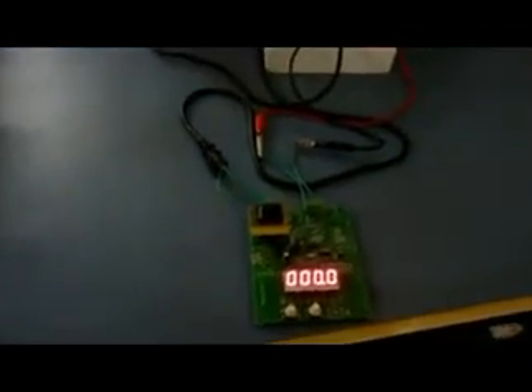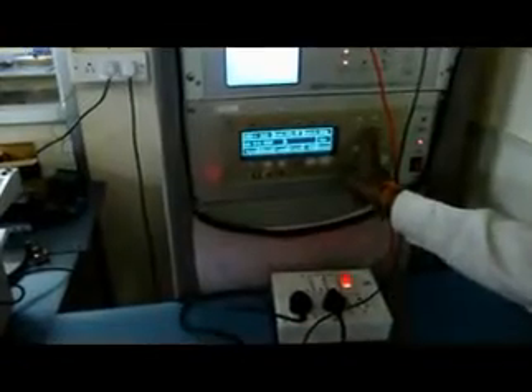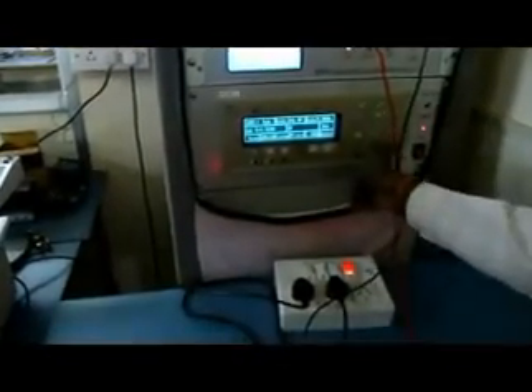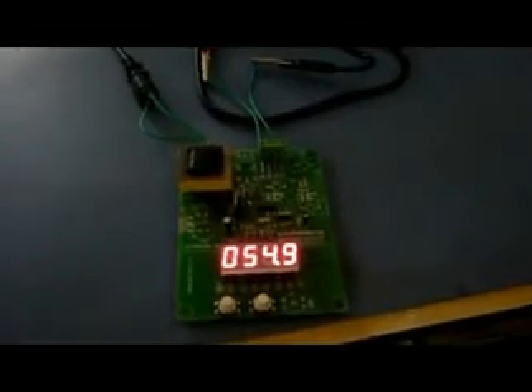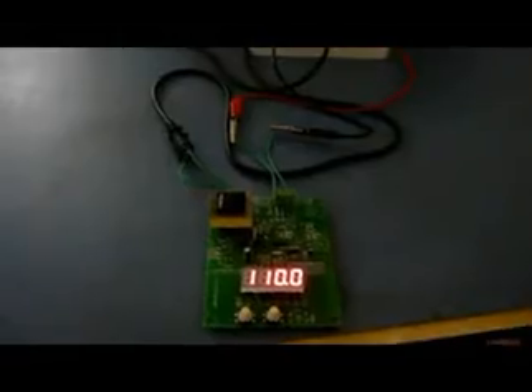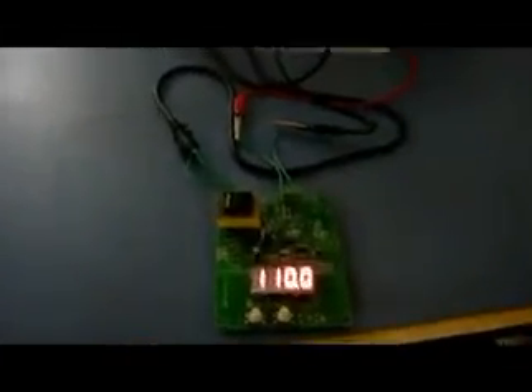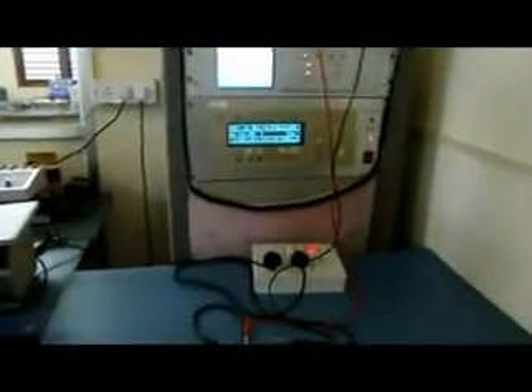We will now feed in 25% of the input. The full scale for the source is at 220 volts, that is 100%. So at 25%, our meter reads 54.9 volts, and on the reference meter we have 54.9 volts, 54.94 to be precise. We will now move to the next point, that is 50%. The DPM reads exactly 110.0, and the reference meter reads 110.04. So we are almost matching the accuracy.